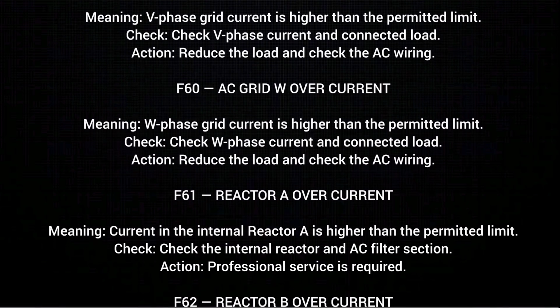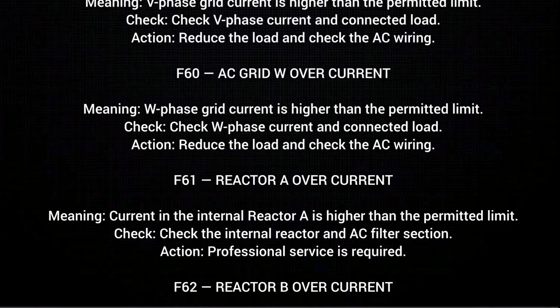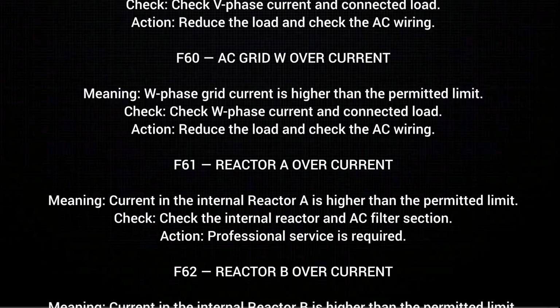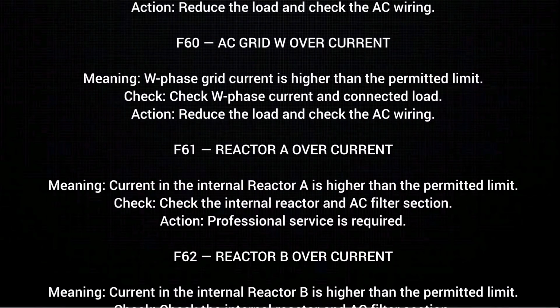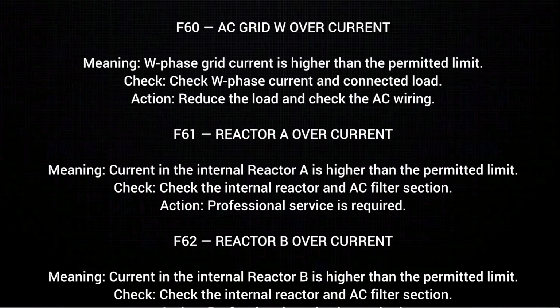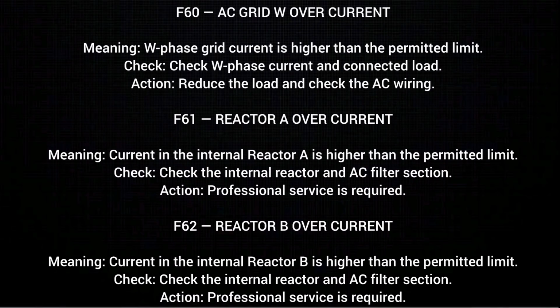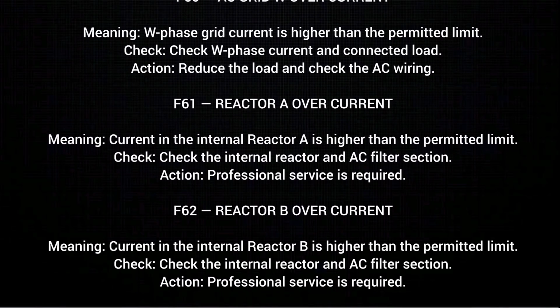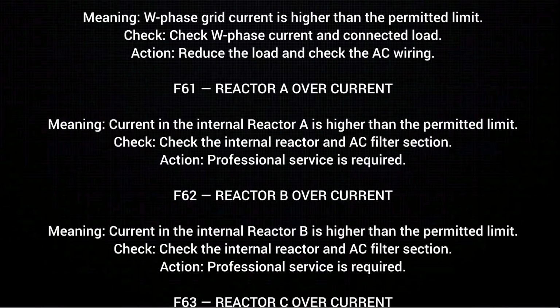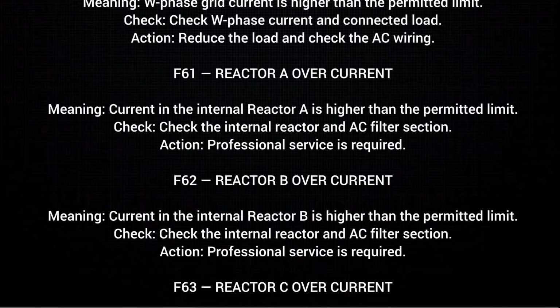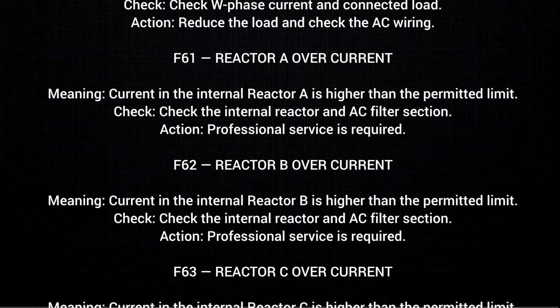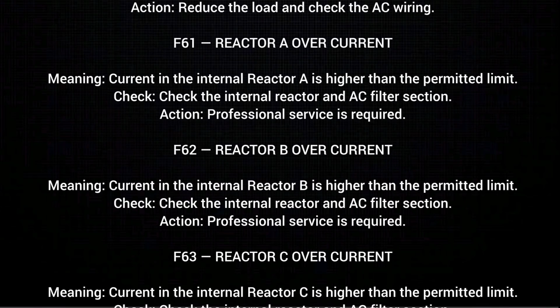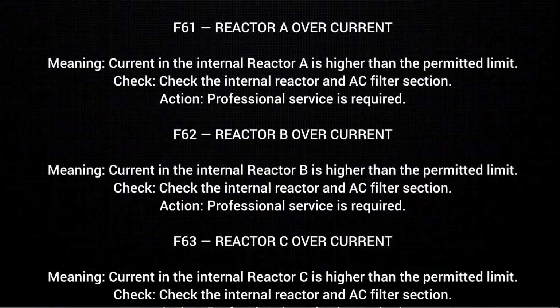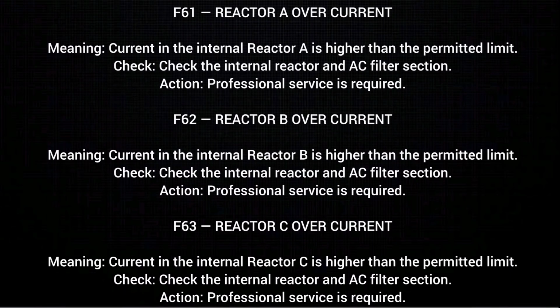F62. Reactor B over current, meaning current in the internal reactor B is higher than the permitted limit. Check. Check the internal reactor and AC filter section. Action. Professional service is required. F63. Reactor C over current, meaning current in the internal reactor C is higher than the permitted limit. Check. Check the internal reactor and AC filter section. Action. Professional service is required.